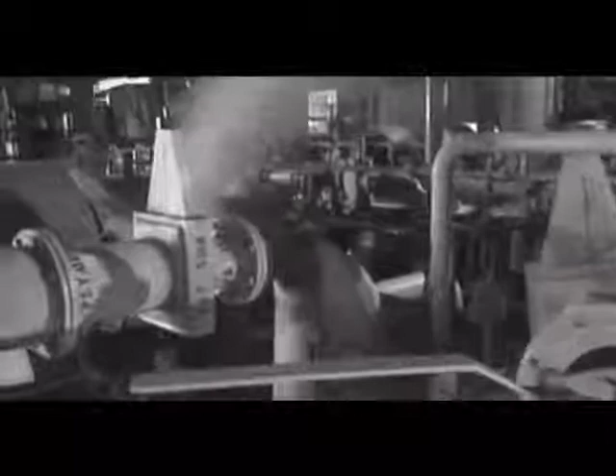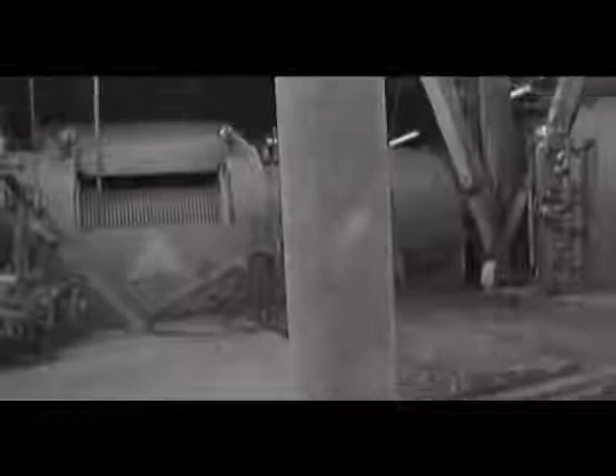But there was a problem with line B. Hydrates were forming at a high rate. Hydrate, which occurs in processing oil coming out of the ground, is nothing more than ice with a little hydrocarbon in it. However, if you think ice is an irritant in your house plumbing, you ought to see it form in a hydroprocessing line. It can totally stop the process. The methanol injection system, which essentially puts antifreeze into the line, had failed. Line B shut down automatically.